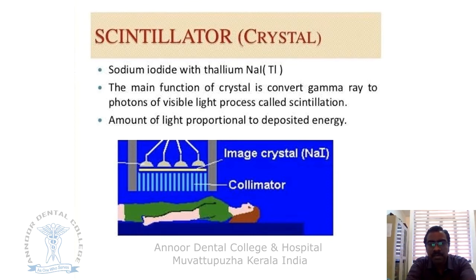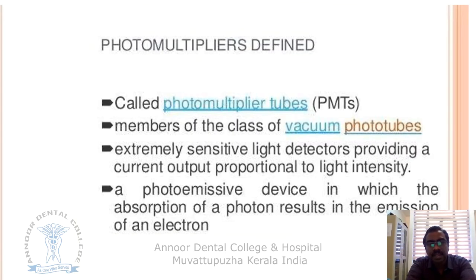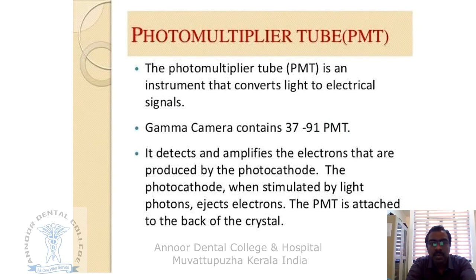Photomultiplier tubes (PMTs) are placed in a vacuum and are extremely sensitive to light. A photoemissive device is one in which absorption of a photon results in the emission of an electron. The photomultiplier tube converts light to electrical signals. A gamma camera contains 37 to 91 photomultiplier tubes. They detect and amplify electrons produced by the photocathode — when stimulated by light, the photocathode ejects electrons. The PMT is attached to the back of the crystal.